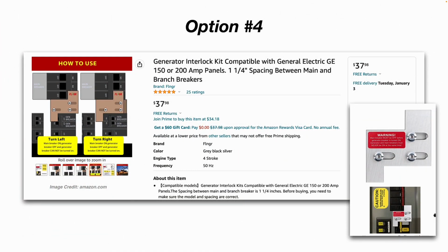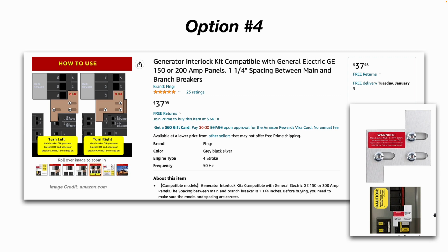Option 4, this is what I would go with. I plan on doing one of these on my house in the future. It's called an interlock kit. In the simplest of terms, it's basically a little metal bracket that you slide left to right or up and down, depending on the make and model of your circuit breaker panel. And it prohibits the main breaker on your panel from being on at the same time that the generator breaker is on. So this little metal sliding bracket only allows one or the other to be on at any given time. Because again, we don't want to accidentally backfeed electricity into the city wires while the linemen are working on it. That could be obviously deadly for them.